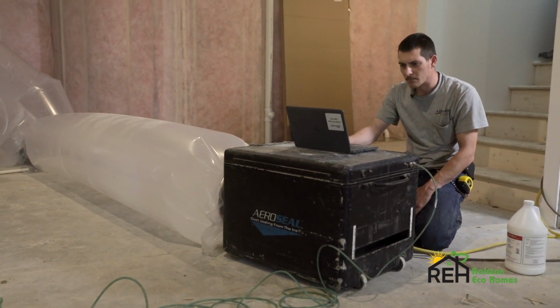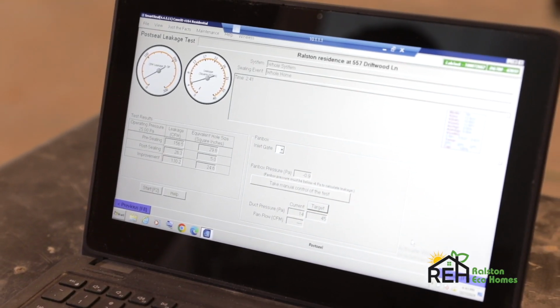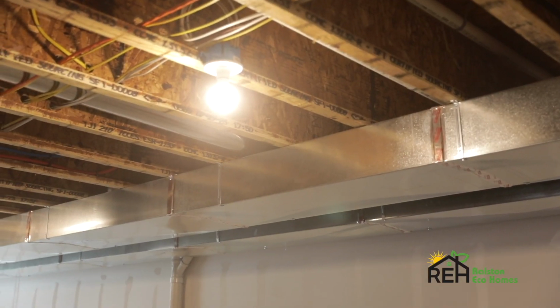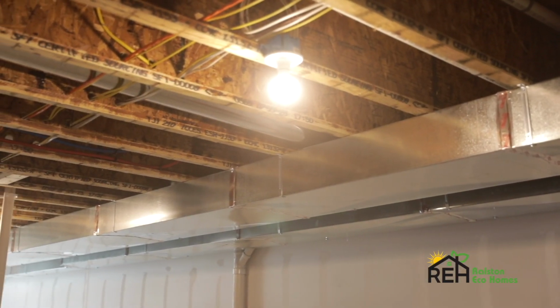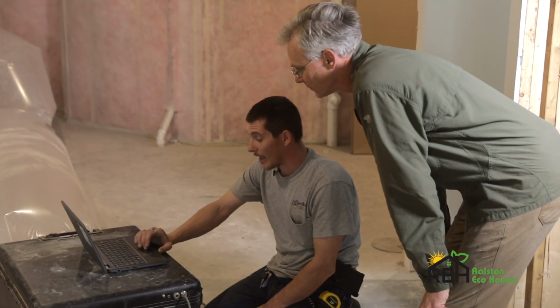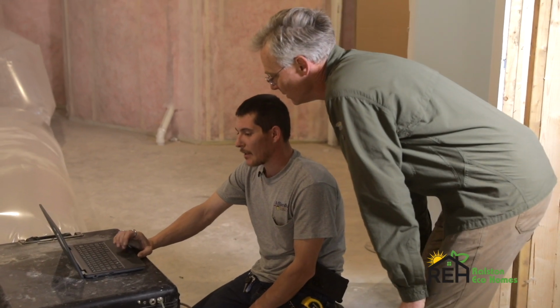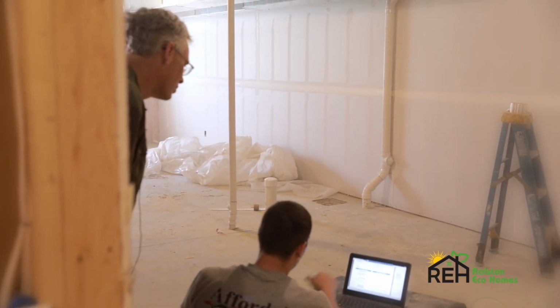So if this house is right around 2,600 square feet, I think the number is like 156 CFM. So we're gonna try and get it down to in the 70s. That way we know it's definitely gonna pass. It's definitely, as much leakage as you can fix, the better off the system's gonna be and the better off the home's gonna be.